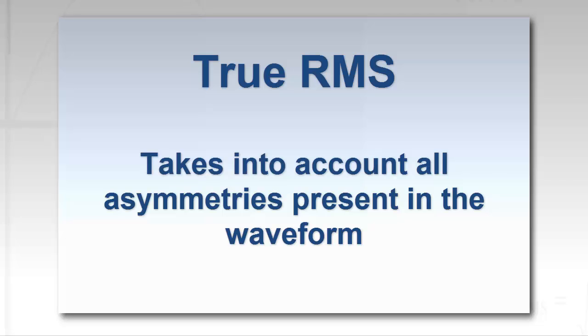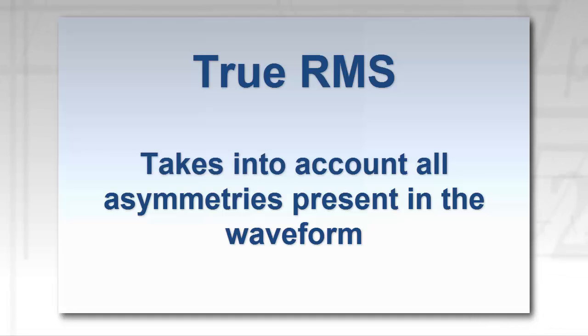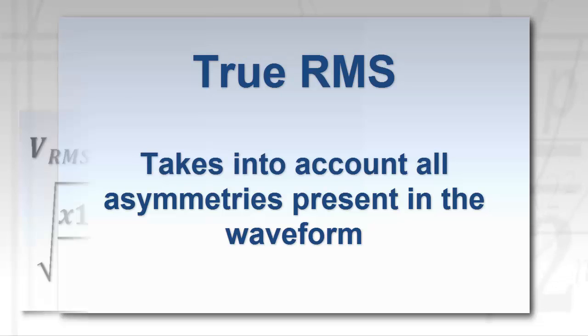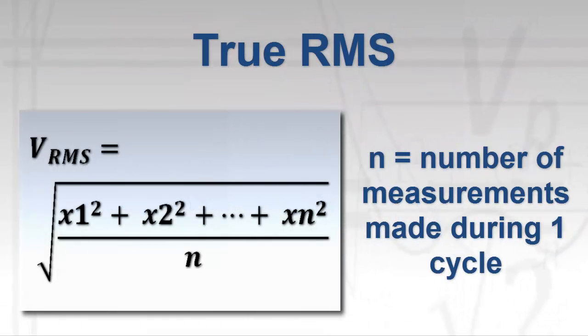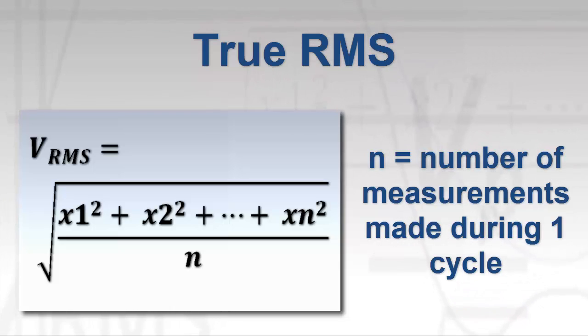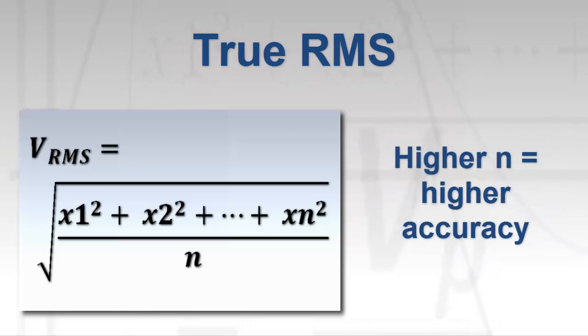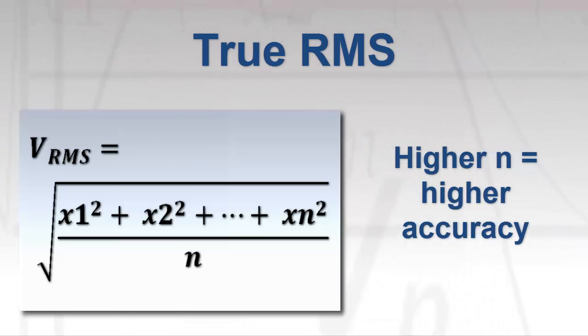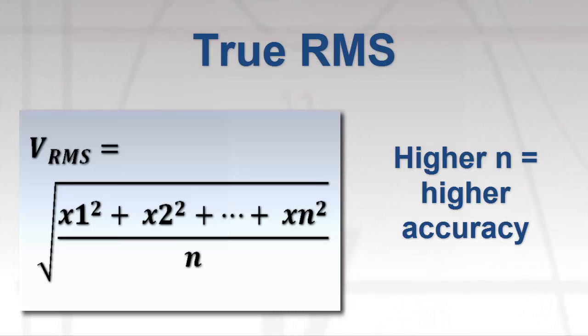True RMS involves a more advanced mathematical calculation that takes into consideration all nonlinearities and asymmetries that may be present in the AC waveform. In this equation, N equals the number of measurements made during one complete cycle of the waveform, or sample rate as it's termed. The higher this number is, the more accurate the RMS calculation will be, because the higher the value of N, the higher the order of harmonics this formula can accommodate.